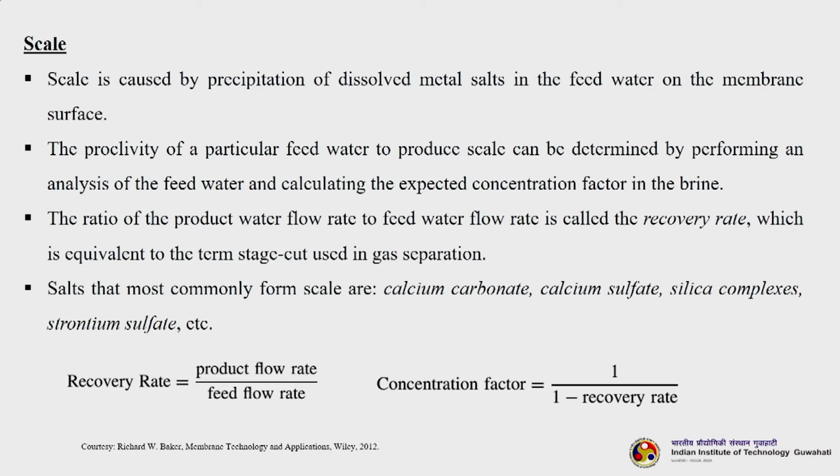Salts that most commonly form are calcium carbonate, calcium sulphate, silica complexes, strontium sulphate, etc. Your recovery rate is given by product flow rate divided by feed flow rate, and the concentration factor is 1 over (1 minus recovery rate).